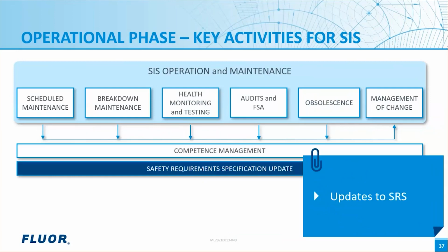We know that SRS is a live document and must be updated for any change during the operational phase. The responsibility for updating SRS shall be part of the operation and maintenance plan. Before changing components, as discussed in breakdown maintenance or obsolescence, reperform SIL verification, update the SRS, and all relevant test procedures to ensure that the integrity requirements are met.